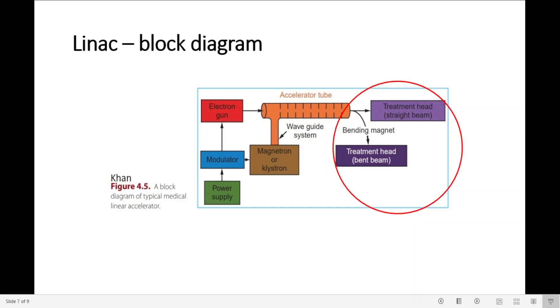Depending on the machine design, they will or will not have a bending magnet. The bending magnet is to bend the electrons, usually about 90 or 270 degrees towards the target.